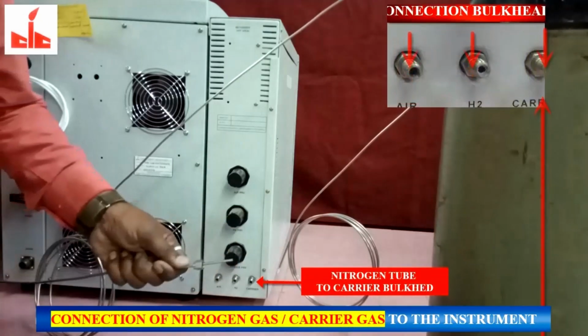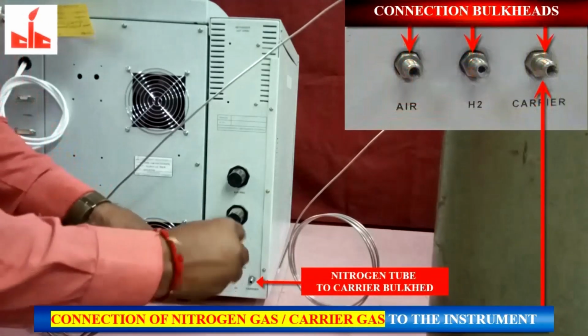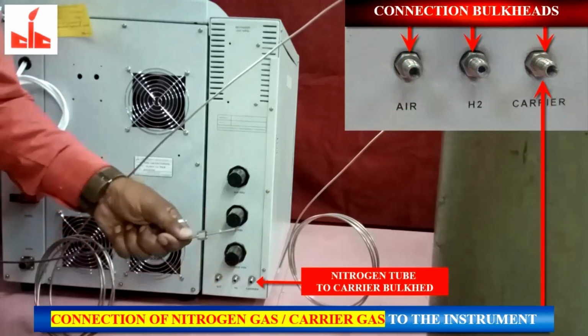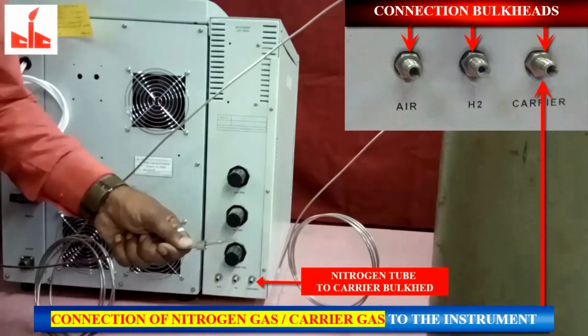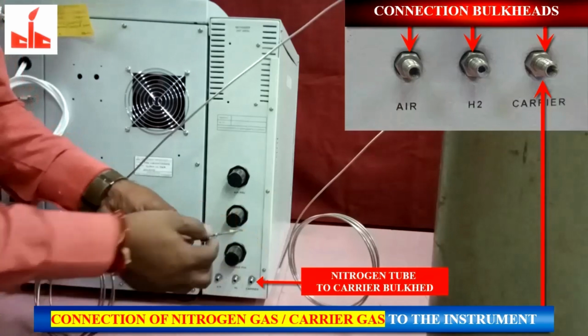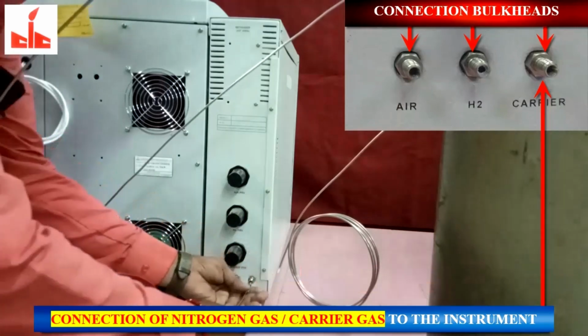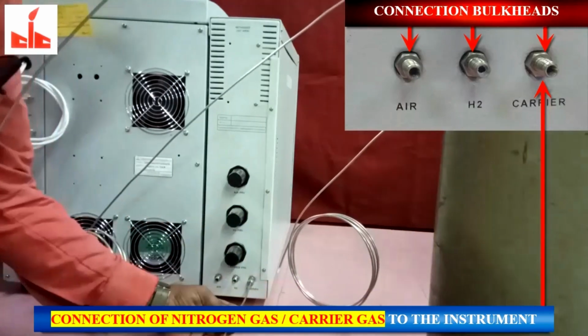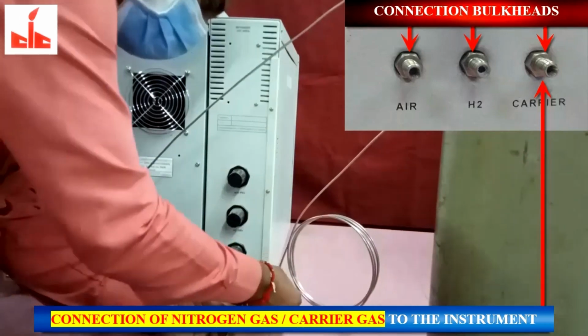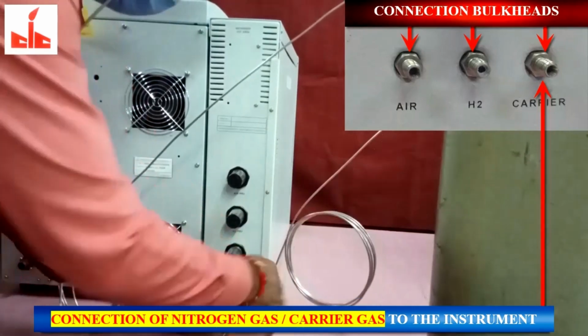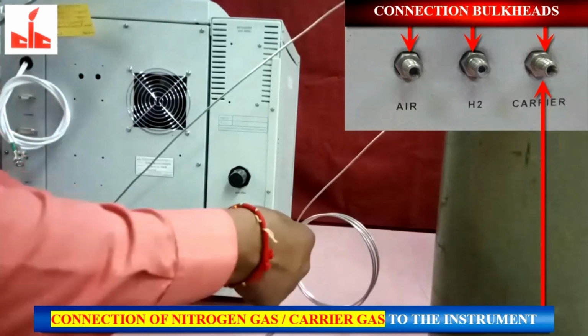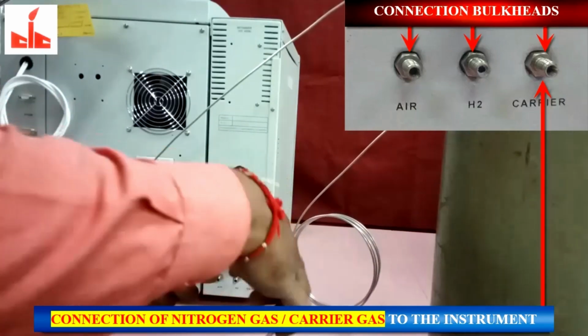Connection of carrier gas tube to the instrument. Here we are using nitrogen gas as a carrier. Connect nitrogen gas tube to the carrier bulkhead of the instrument, same way: bite ferrules, and put Teflon tape on SS tube, as per previously mentioned procedure. Then connect hydrogen and zero air tubes.